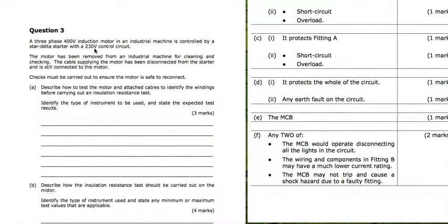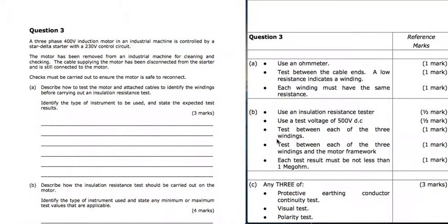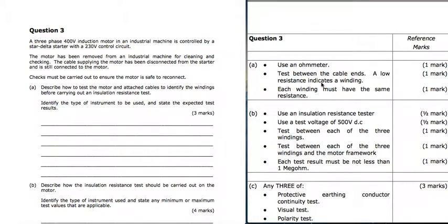Question 3, 3-phase 400 volt induction motor, and we've got star delta starter 230 volt control circuit. We've removed it for cleaning. We're going to check it's safe. Describe the test. Test the motor and attached cables to identify the windings before carrying out an insulation resistance test. So how we're going to identify the windings? We're going to use an ohm meter, and we're going to test between the cable ends, and we're going to look for a low resistance. And a low resistance is going to indicate the winding. And obviously each of those windings must have the same or very similar resistance. And that's how you know you've got the two ends of one winding.